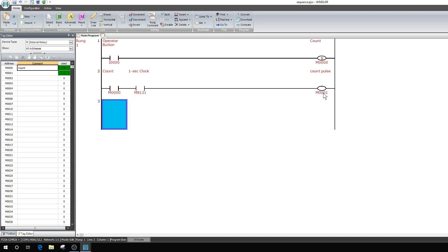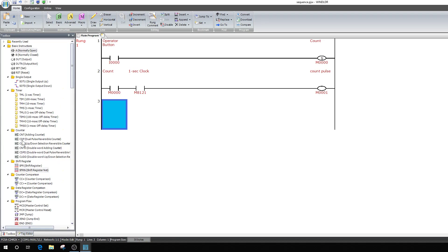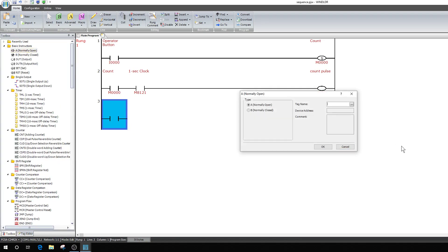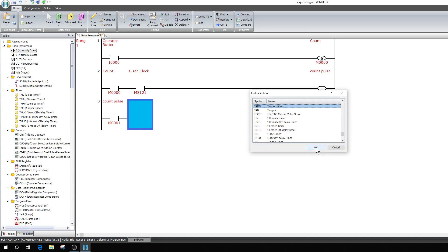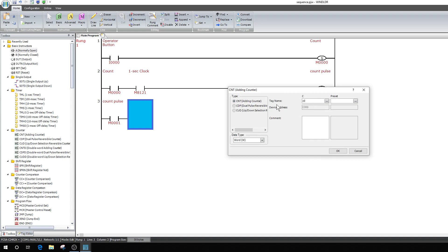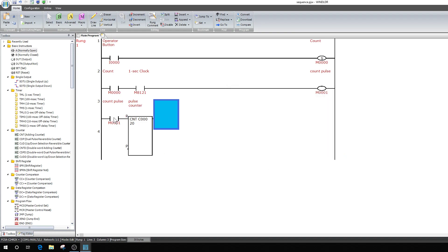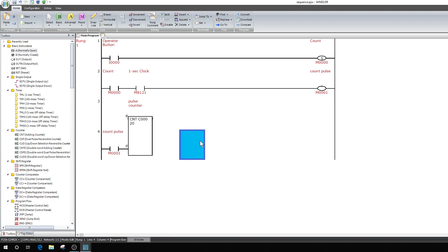So M1 is my count pulse. Now I'm going to count it. I'll put another normally open contact referencing M1, then add a counter — a CNT adding counter. Counter C0. I'm going to go ahead and preset it for 20 seconds. This is going to be my pulse counter. I made a mistake placing the reset in the wrong spot — I'll cut and paste it to the correct location: this pulse needs to be counted right here.